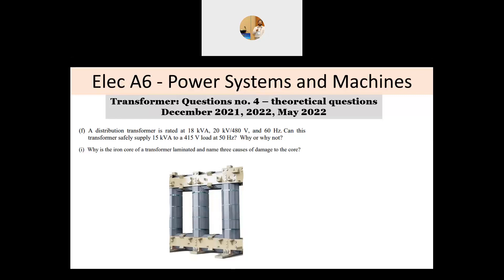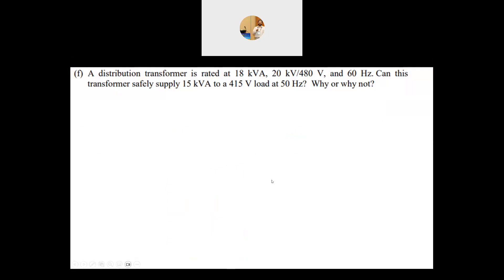Let's start with the first question. A distribution transformer is rated 18 kVA, with a voltage ratio of 20 kilovolt to 480 volt, operating at 60 Hz. The question is: can we use this transformer to supply 15 kVA instead of 18 kVA, but at 415 volt and 50 Hz? Why or why not?